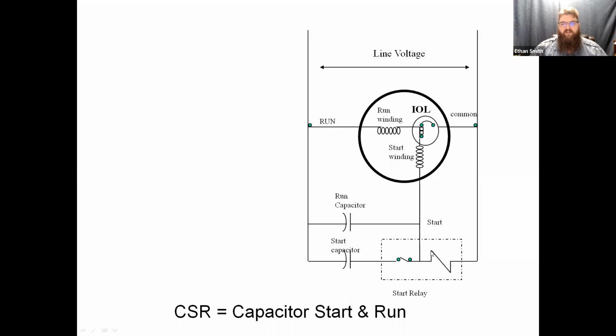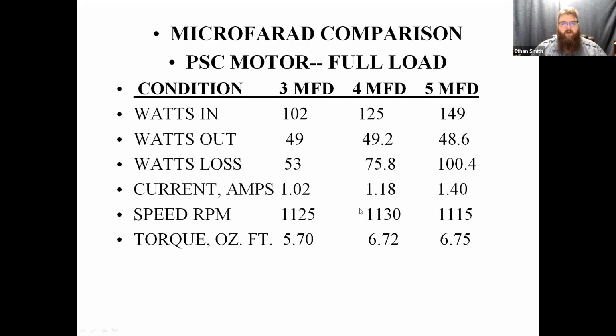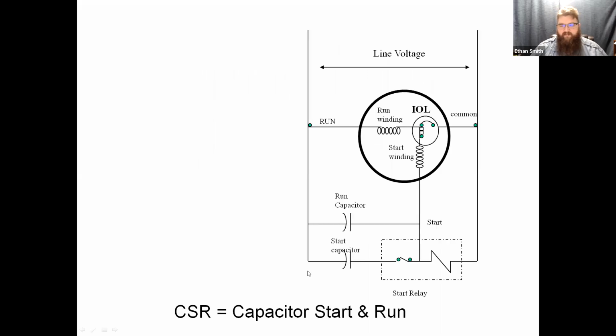So once this motor starts spinning and generating that back EMF that we talked about last week, it's going to engage this relay, which will break the circuit between the start capacitor and the start winding. Okay, that essentially drops that capacitor out of circuit and allows the compressor to continue running with just the run capacitor in circuit. So we go back to this chart where instead of just running with a single run capacitor all the time, we conceivably could put a 5 microfarad capacitor in there as a start capacitor and use that to get our extra starting torque. But once the motor's spinning, drop that capacitor out and run it on a 3 microfarad capacitor for efficiency. Does that make sense? Any questions about this? No.